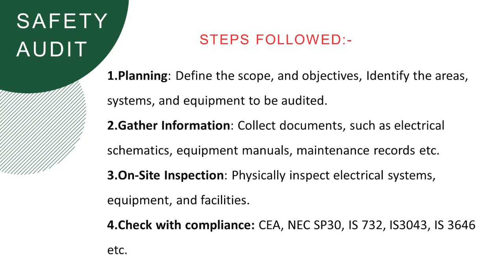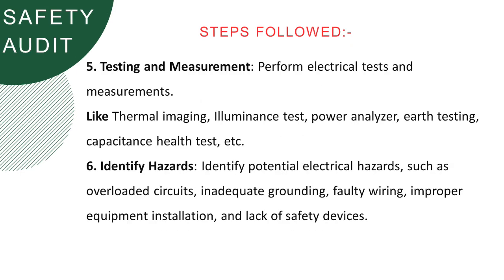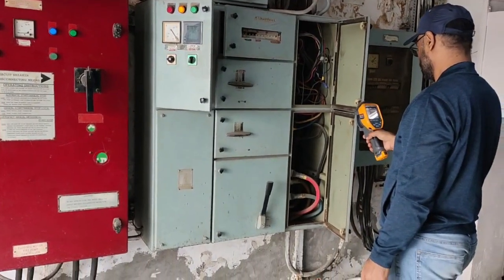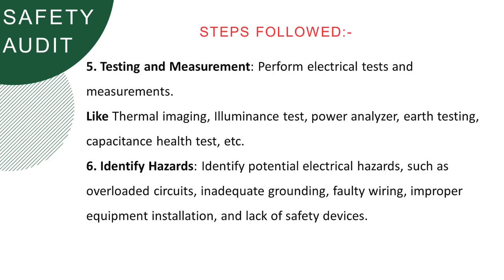After the walkthrough audit, the next step is testing and measurement. Everything cannot be checked by inspection alone, so testing is done on your electrical system. Thermal imaging is conducted to check the temperature of your electrical system. Any increase in temperature due to loose connections, overheating, or overloading can be detected by thermal imaging.